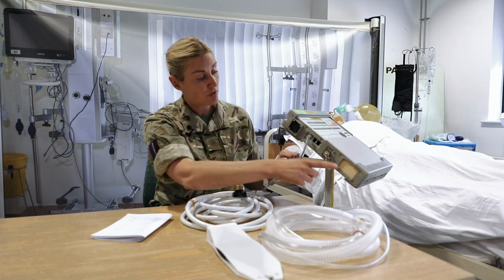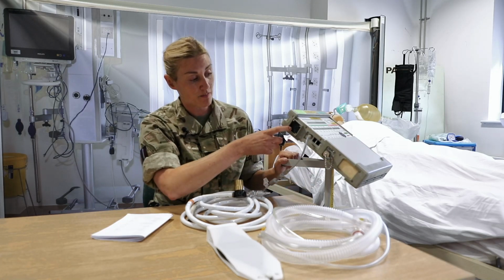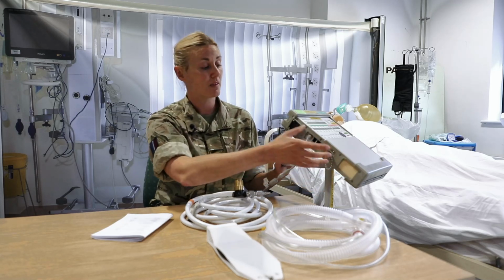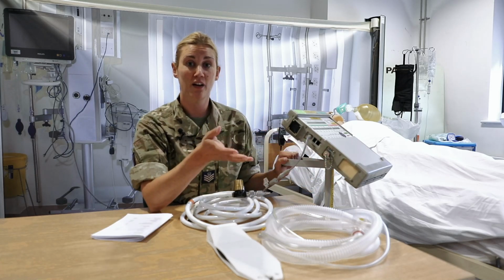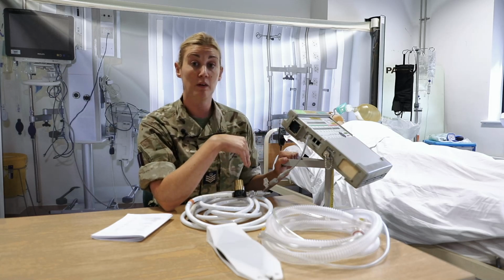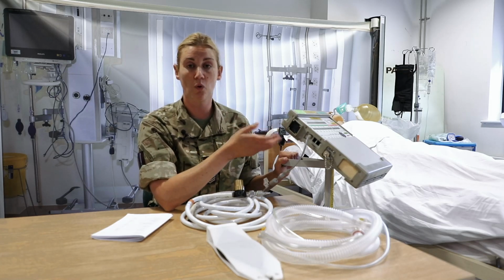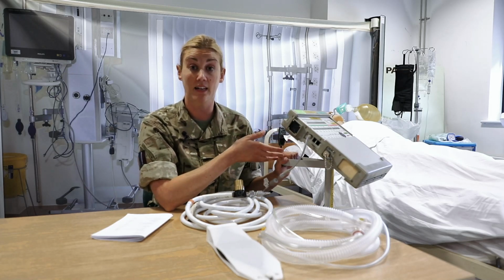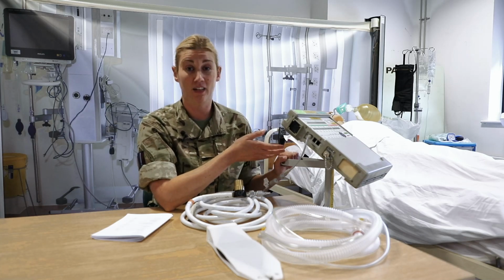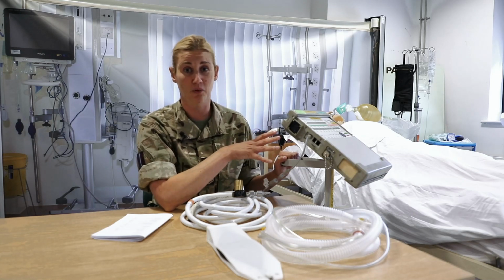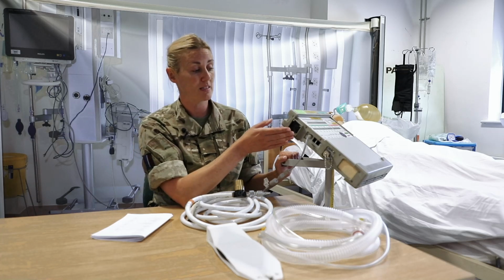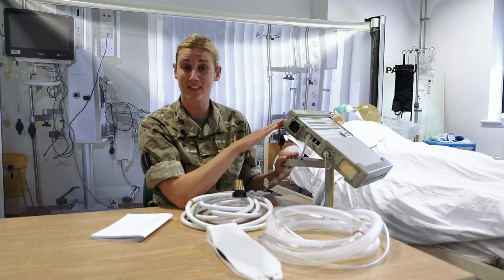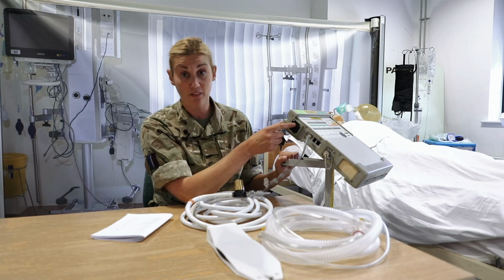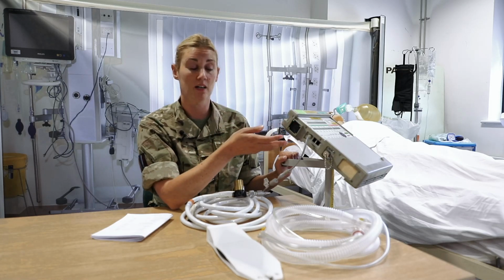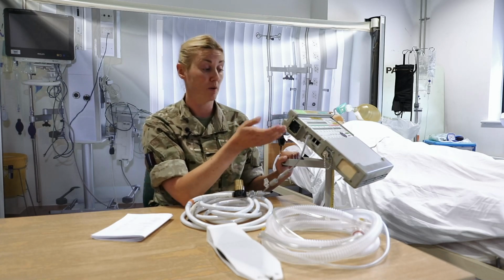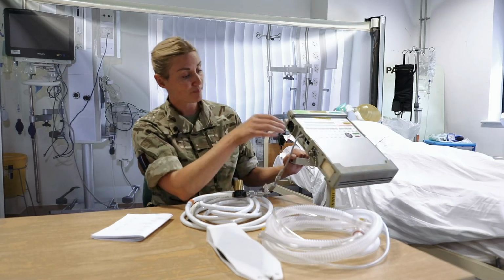We've got two filters here, so we have our fan filter and our air inlet filter. These two filters, as you've learned from the orientation video, need to be removed and cleaned in warm soapy water every 30 days or 750 hours of continuous use if they're attached to a patient, obviously. Just remove the ventilator from the patient, take the filters out, wash them, allow them to dry naturally once you've rinsed out all the soap, and then just reapply them.